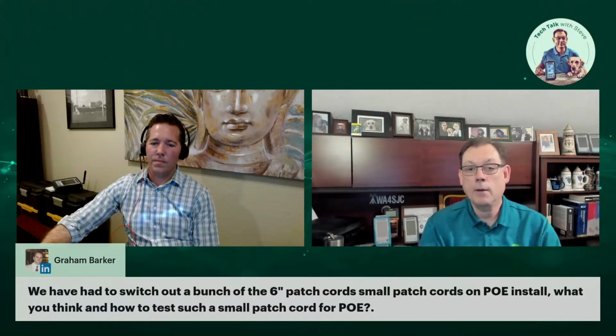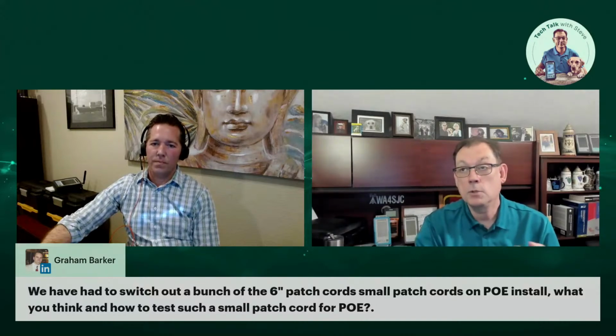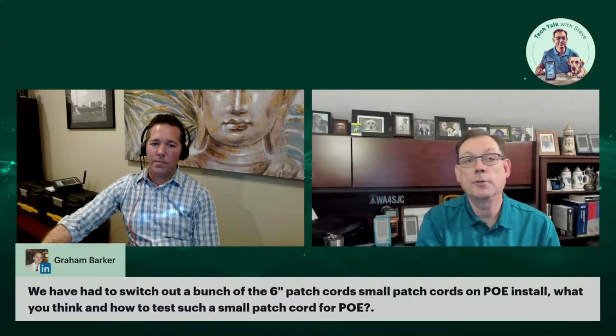I won't use the 6-inch as an example, but if a short patch cord does have issues like resistance unbalance, you'll see that show up in a physical cable test. You could run a cable test with that patch cord and without it to see if it contributes to the resistance unbalance.